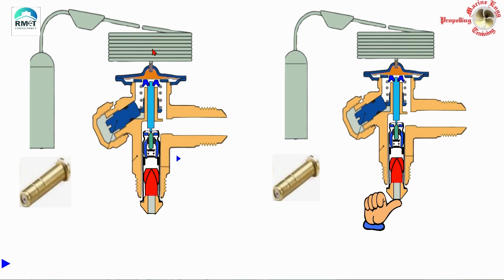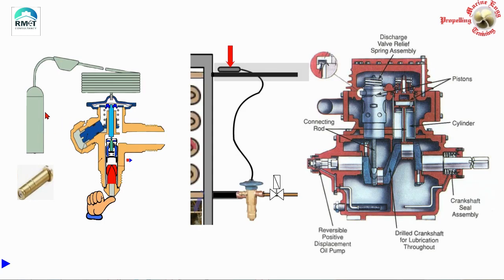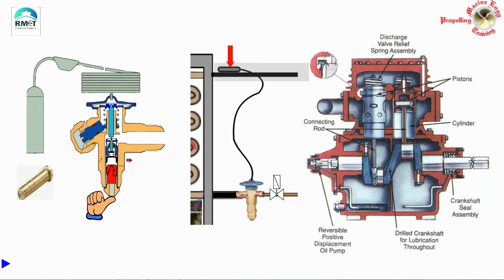Another way to verify: when you push the orifice back in, you can feel the spring — the superheat spring — compressing and expanding under your thumb. This test confirms that the gas inside the bulb is present and the valve is in good working condition. Now suppose the gas has leaked out: the spring will press on the diaphragm and there is nothing to resist from the top, since the bulb gas pressure is no longer there. When you try to fit the orifice, you will see no gap and feel no springiness — that tells you the expansion valve needs to be renewed.